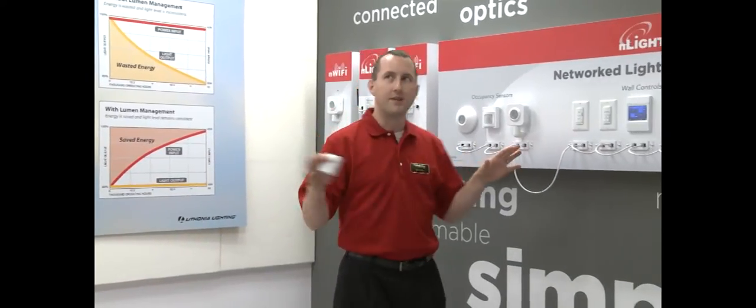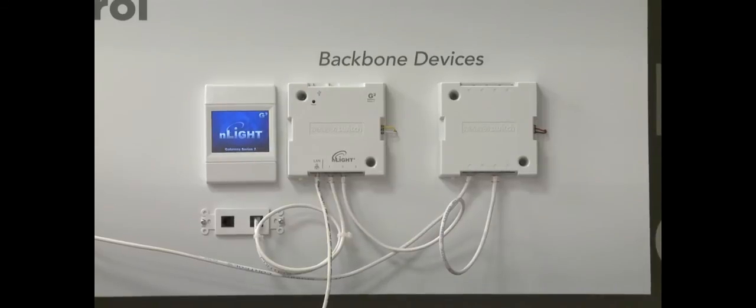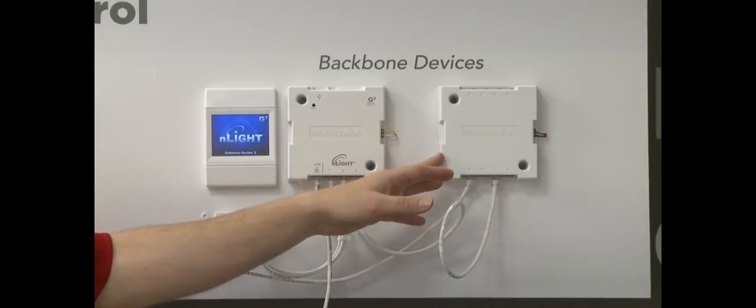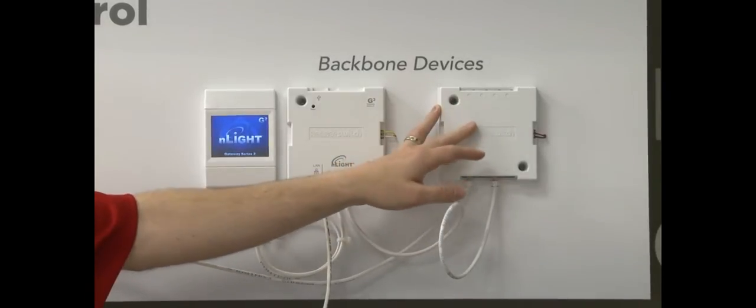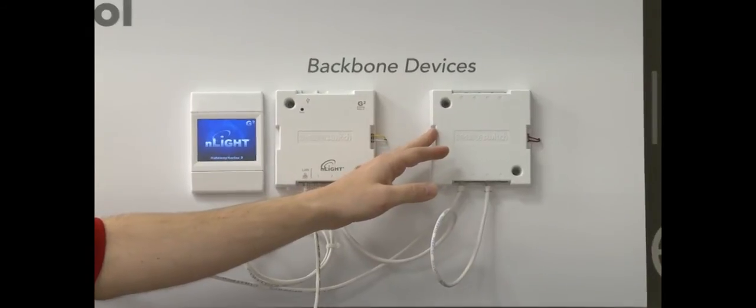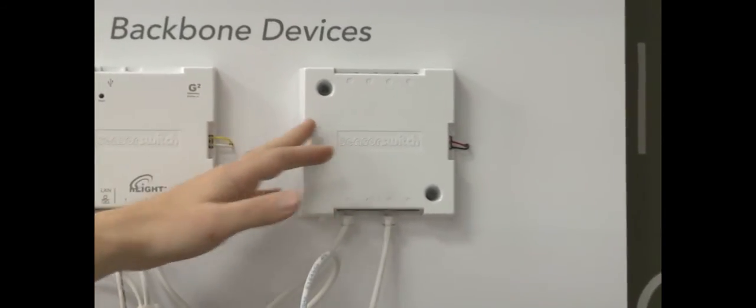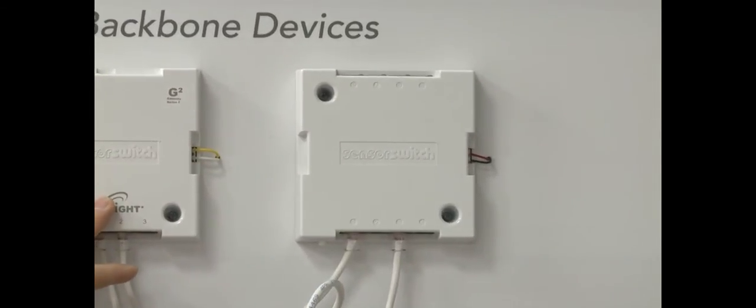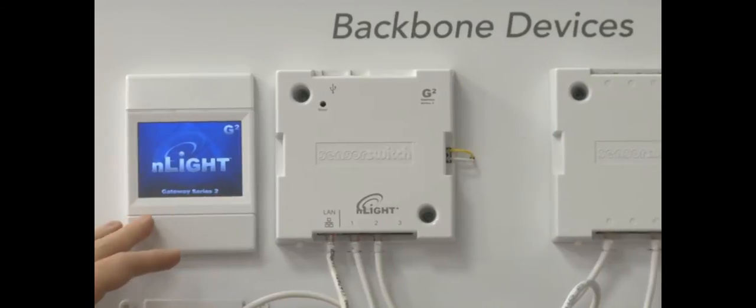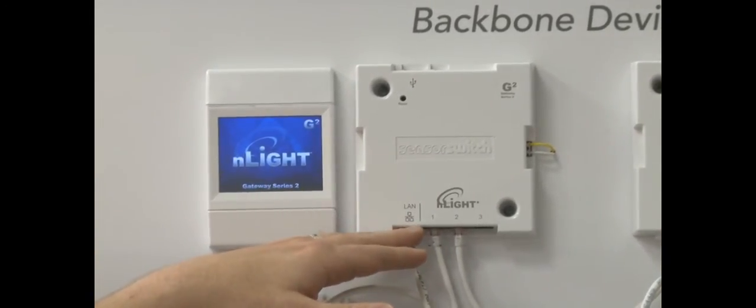This would be an example of one Nlight zone. Over the course of the building, you have many zones of devices. They all would get connected together in a backbone into devices we call bridges. You can have up to eight zones plugged into each bridge. As many bridges as would be necessary would then be connected up, eventually finding their way back to a device we call the gateway. The gateway has both the time clock as well as the interface to an Ethernet LAN.